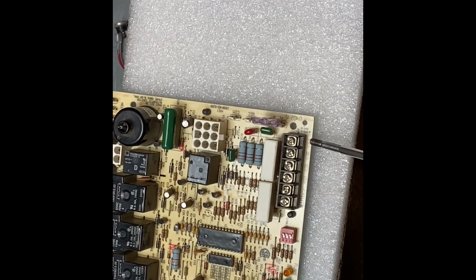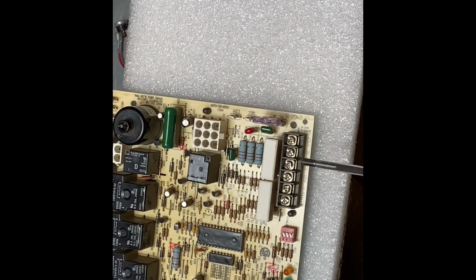So C is for common. Some of the digital thermostats now, you want to put the common wire in so that you make sure that you're powering the thermostat off the transformer. You have R for 24 volt power, you have W for heating, G for indoor fan, Y for a call for cooling. Now notice that I said the letter. You can put any color wire you want, but don't always think that red is going to be R. That's going to cause problems at some point in your career. Whatever wire I connect to R here, I also connect to R at the thermostat.